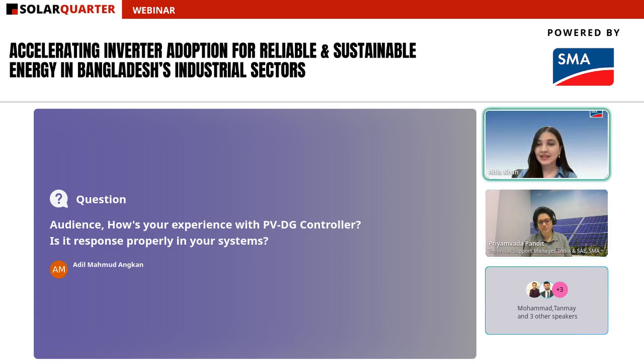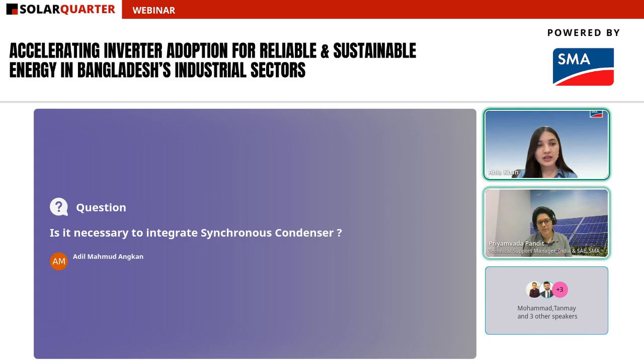Next question: is it necessary to integrate a synchronous condenser? This depends on your system size. We have to evaluate project by project - total sources available, size of PV, size of condenser, whether you have grid connection or additional sources. All that needs to be taken into account to understand how this integration should be done, or whether it's needed at all.